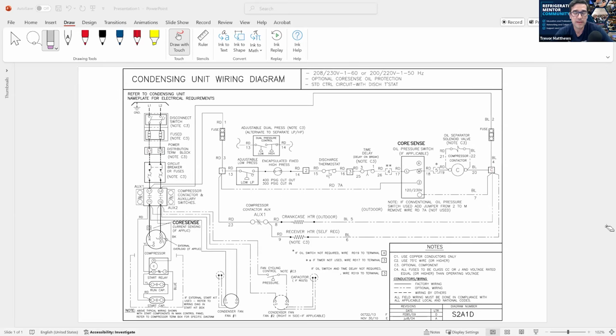So the important thing is to understand, and I say this time and time again, I do a lot of these trainings. When I'm in my supermarket training, CO2 training, the biggest thing is to understand how to read a wiring diagram. The first thing you got to know is that when you're looking at it, the power is off. So any switch that is closed and the contactor coil gets energized, that will open up some relays and contactors. So you want to understand that. You always want to test across loads. That is so, so important.